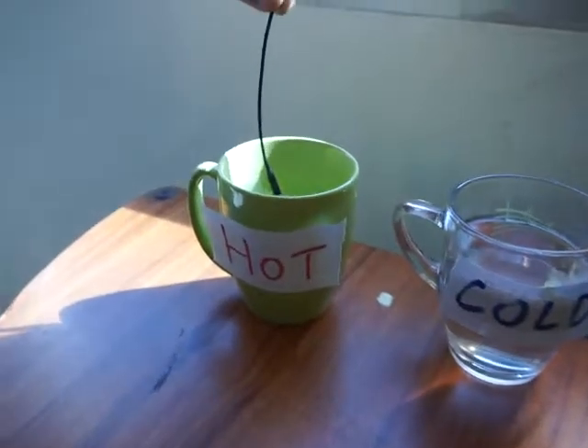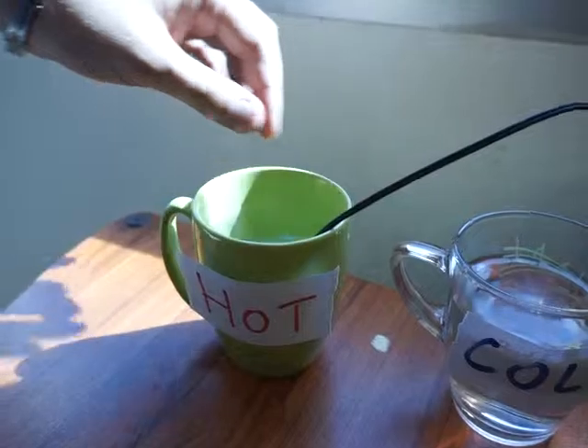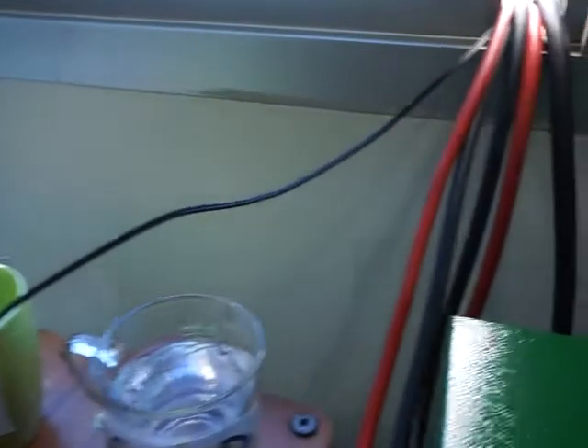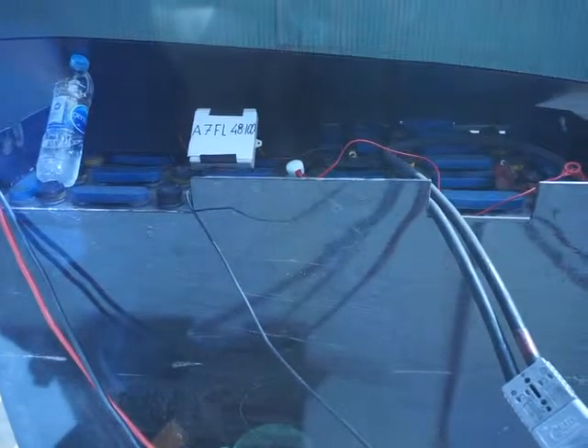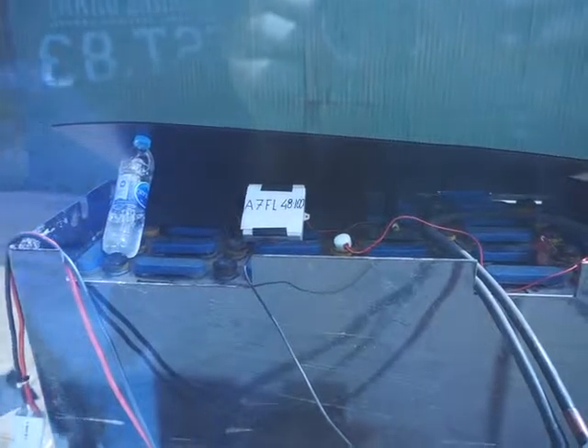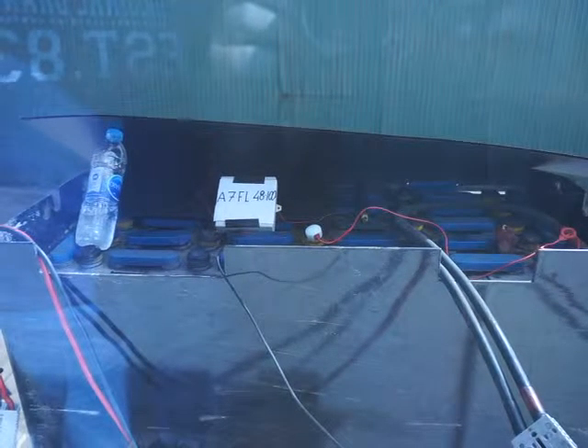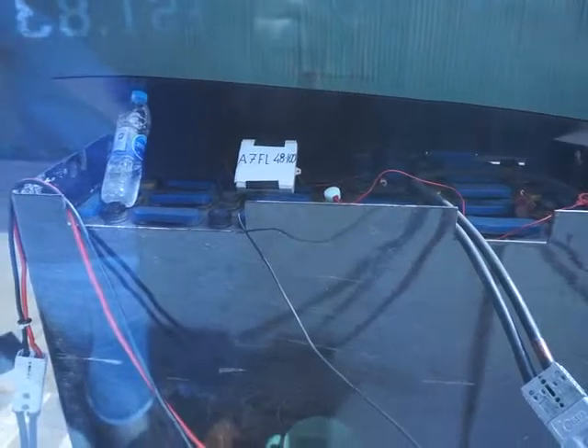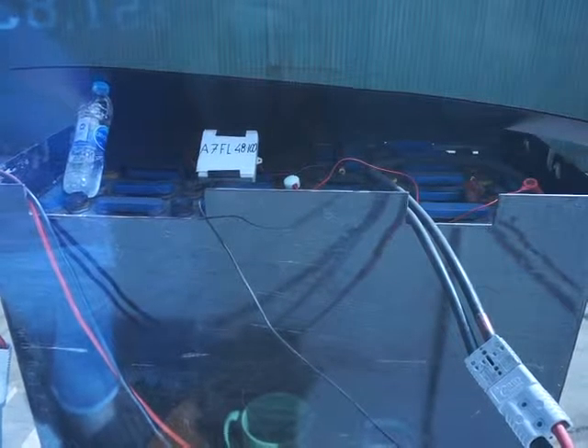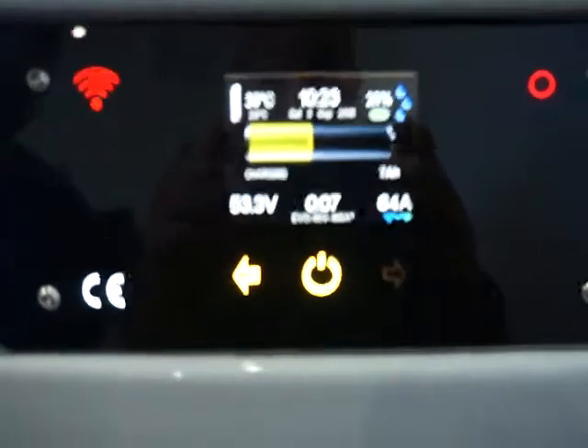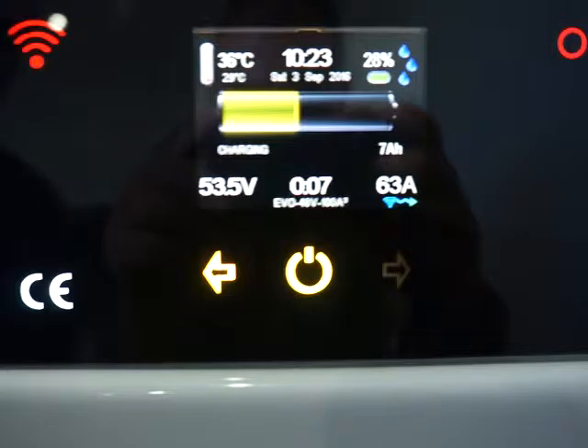Now I will try to go from cold to hot. The charger is set to stop the charge if the temperature of the battery recorded goes above 60 degrees, and to restart the charge when it cools off at 45. So when it stops, the charge will not be cancelled, it will automatically restart exactly where we last saw it.